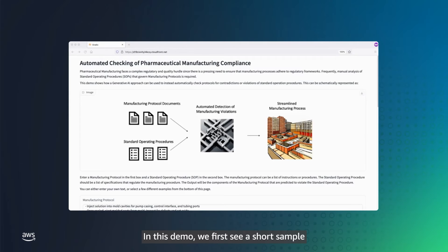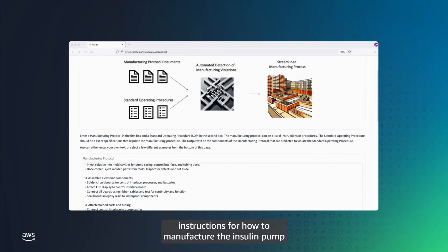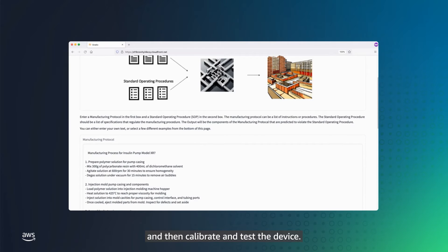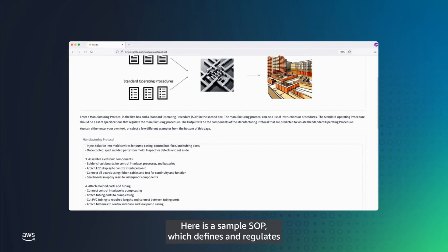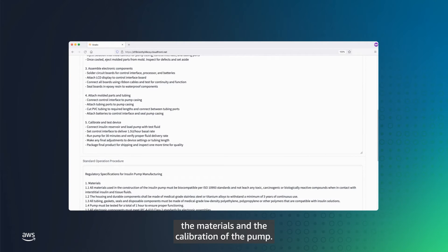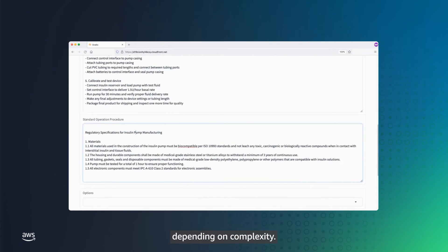In this demo, we first see a short sample of an insulin pump manufacturing protocol. The manufacturing protocol document contains very brief instructions for how to manufacture the insulin pump and then calibrate and test the device. Here is a sample SOP, which defines and regulates the materials and the calibration of the pump. The manufacturing protocol follows one or more SOPs depending on complexity.